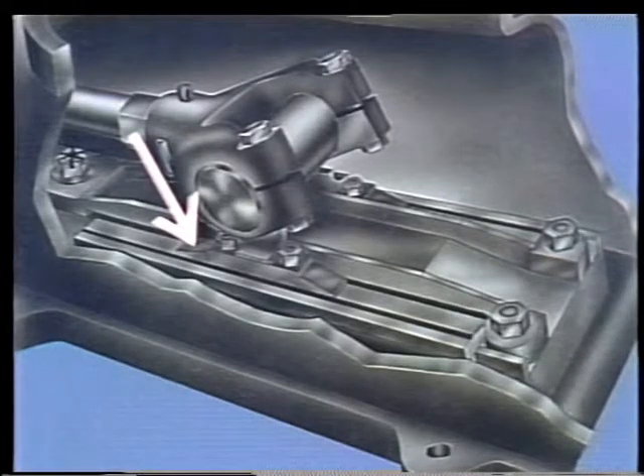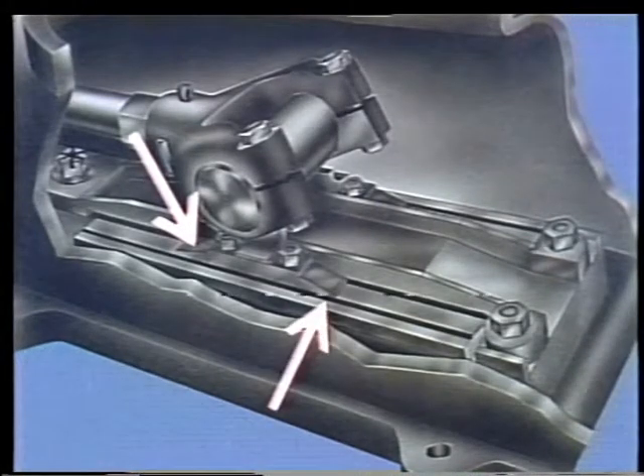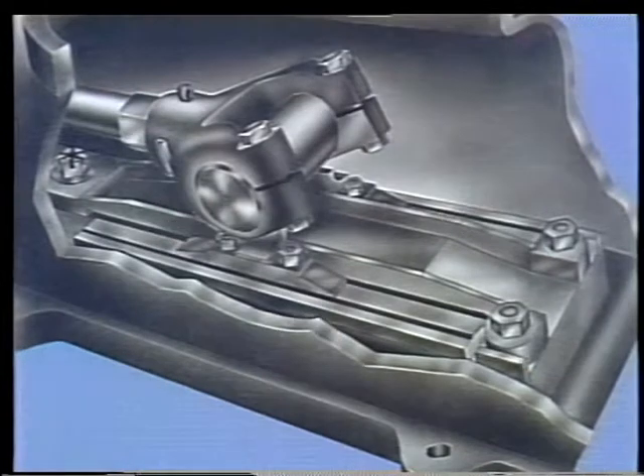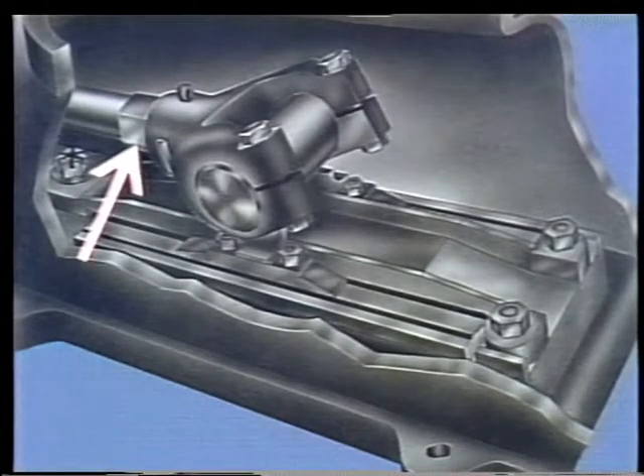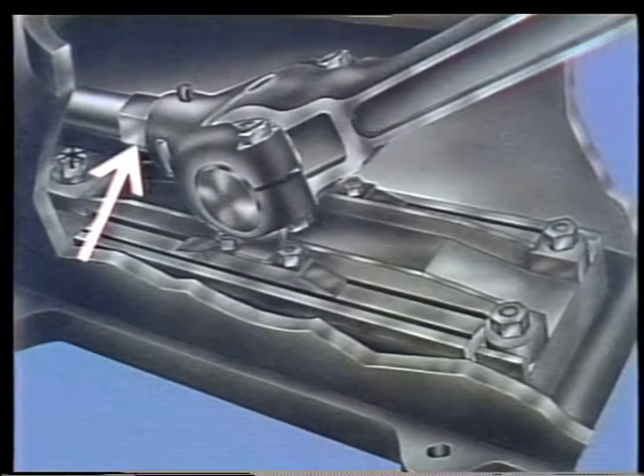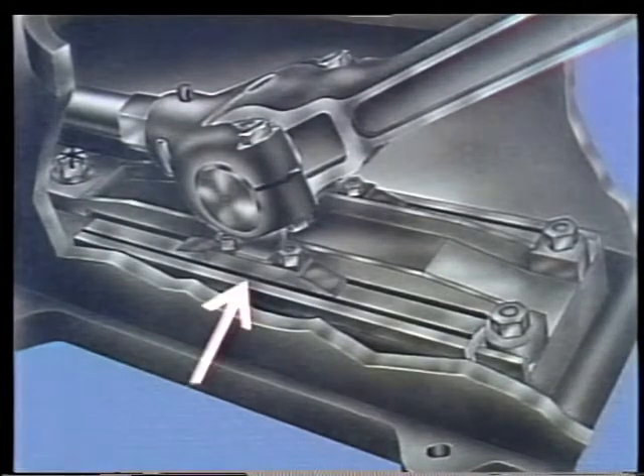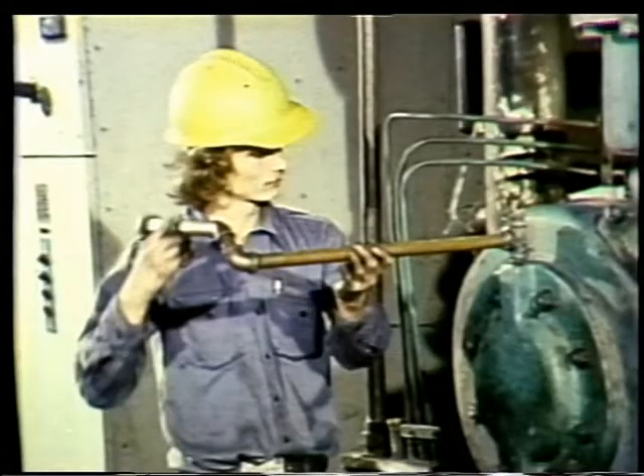The parts of the crosshead show up more clearly here. It has a wearing shoe and two guides, a bottom guide in the frame, and a top guide bar. The piston rod screws into the crosshead here, and the connecting rod attaches to the crosshead here. There are shims between the crosshead and the wearing shoe. By removing or inserting shims in this space, you can adjust the position of the crosshead so that it will maintain the piston rod and the piston in the correct horizontal position. After the crosshead is adjusted, you can reconnect the cooling water discharge pipe to the head and put the compressor back together. Well, now, the reassembly process is complete.